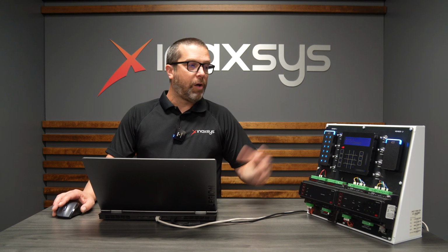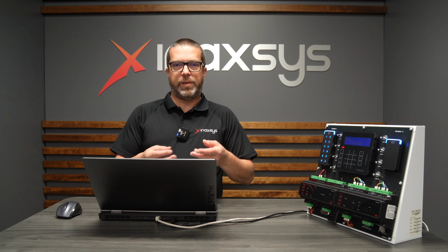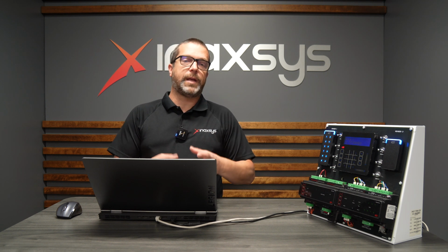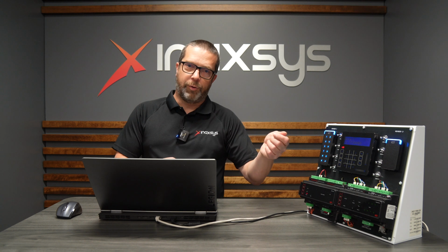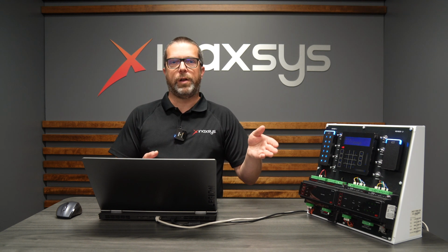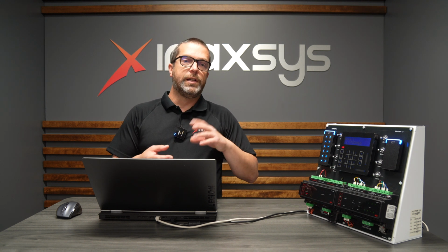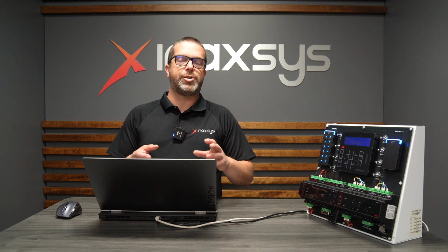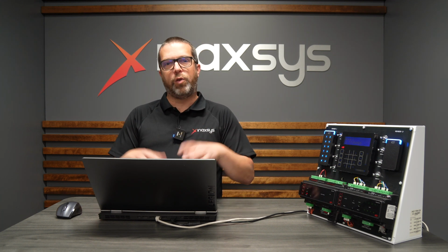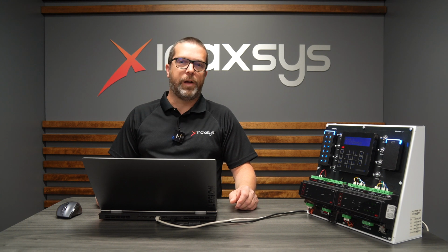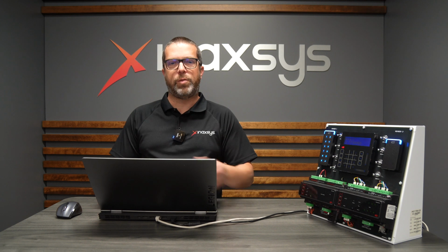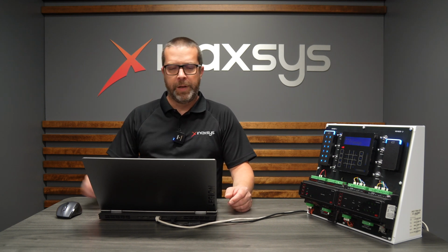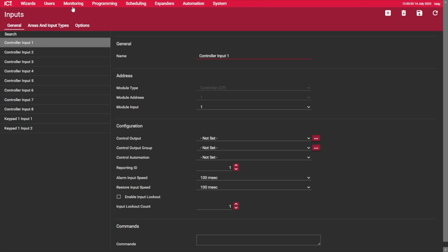Also, depending on how the system is wired up with the elevator company, sometimes they will give you a dry contact that will trigger a zone on a ZX16 DIN, for instance. Sometimes it's voltage that they give you for button feedback. In this case, we have the ISO 16 DIN rail module that will open a zone when you inject DC voltage on it. If you want to know the specifications of voltage that can be used on this module, please refer to the install guide. So back to the testing now.